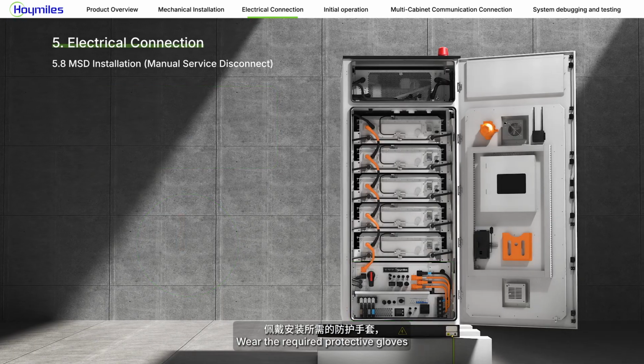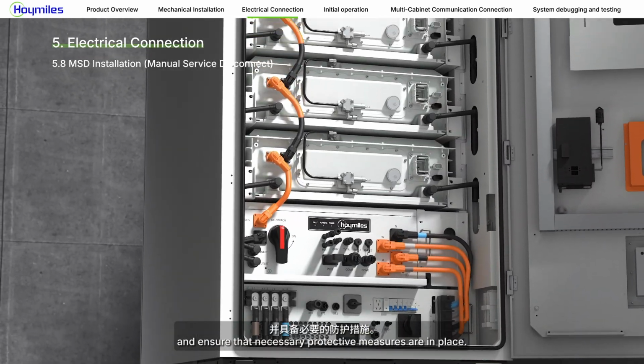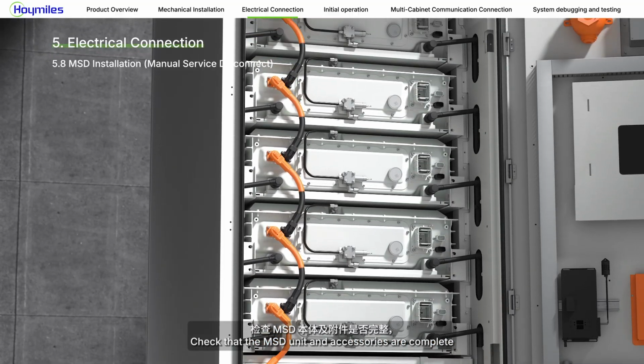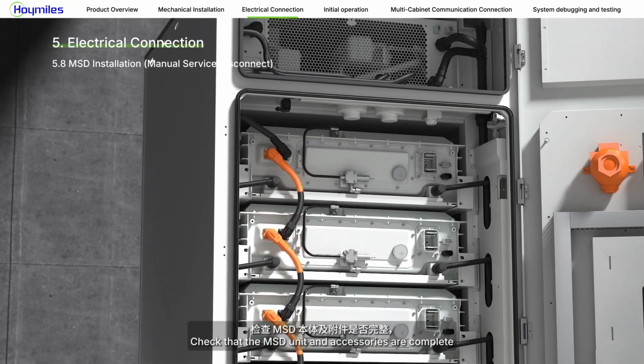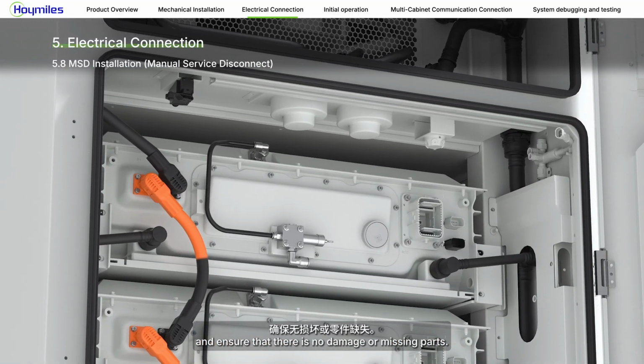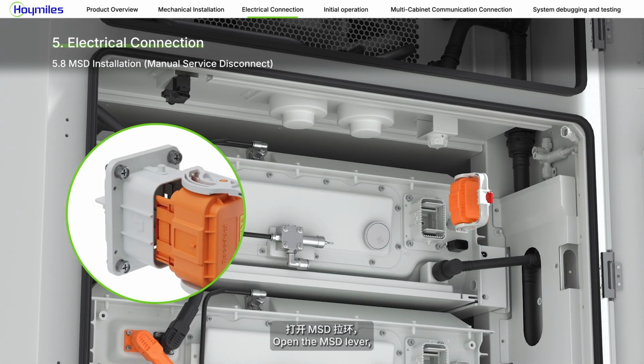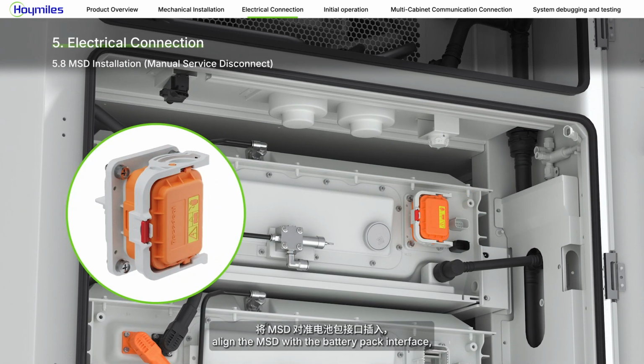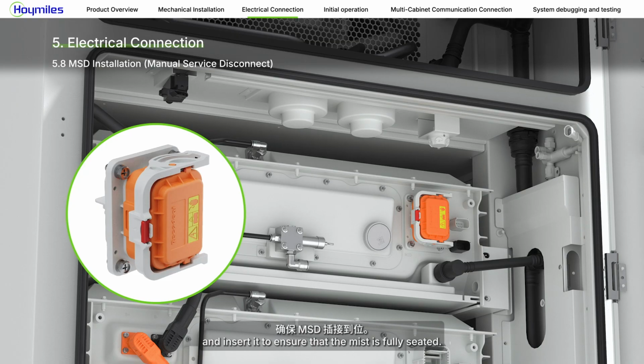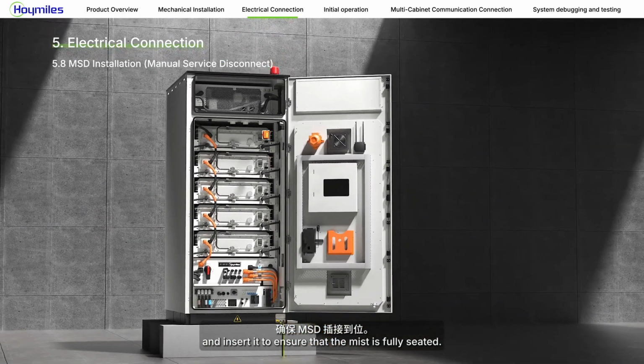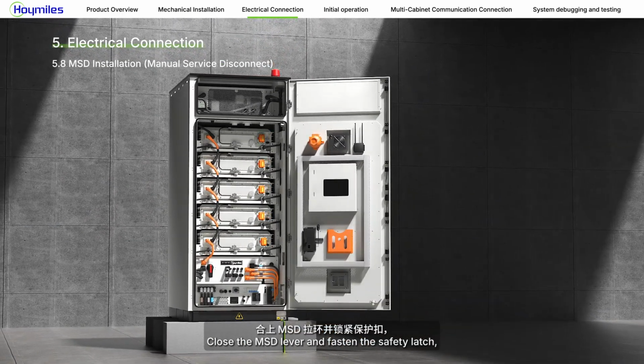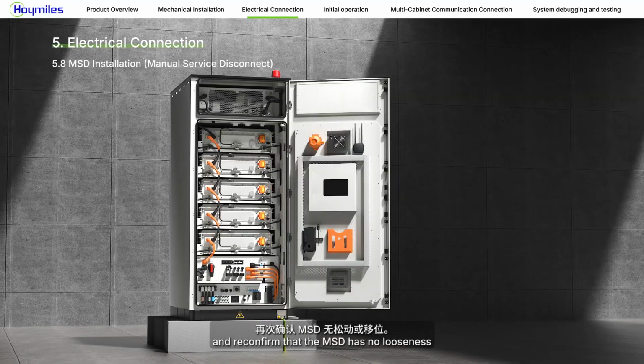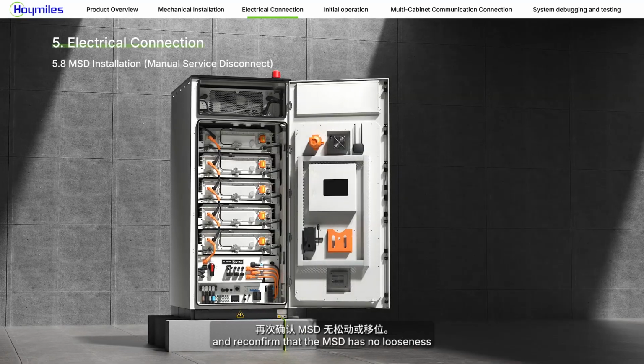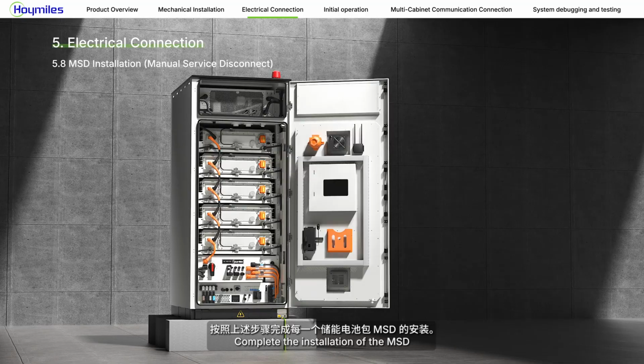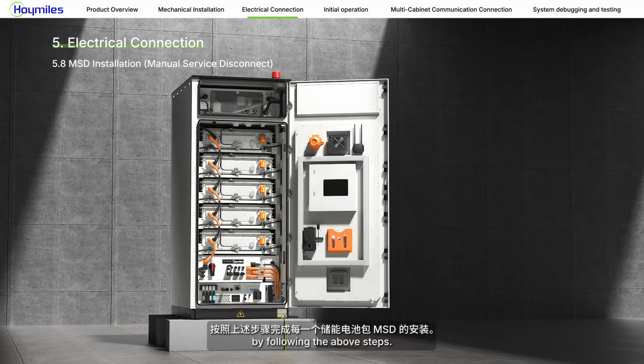Wear the required protective gloves and ensure that necessary protective measures are in place. Check that the MSD unit and accessories are complete, and ensure that there is no damage or missing parts. Open the MSD lever. Align the MSD with the battery pack interface and insert it to ensure that the MSD is fully seated. Close the MSD lever and fasten the safety latch, and reconfirm that the MSD has no looseness or displacement. Complete the installation of the MSD for each energy storage battery pack by following the above steps.